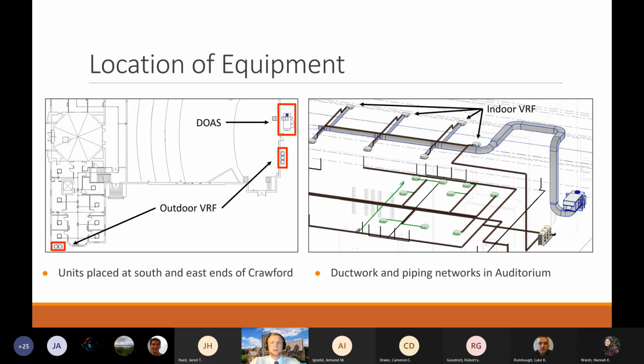So we designed the system with the assumption that we couldn't place any of the heavy outdoor equipment on the roof because it wouldn't be able to support the weight of the units. So we chose to position the DOAS and the 3 outdoor VRF units for the auditorium outside the east wall on the patio that is between Crawford and the adjacent building next to it. And the other 2 units would go on the south end where there's already some existing mechanical equipment. And then the ductwork and piping networks were created in the Revit model to connect the DOAS and the outdoor units to the indoor units, which you can see in the picture to the right there.